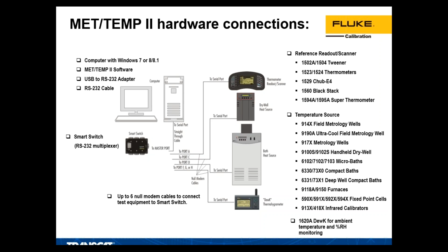In the setup, you choose your reference readout and your temperature sources, and you can even collect data from the 1620A DewK temperature and humidity monitoring unit. That way you don't have to manually record the temperature and humidity during the test — it's all done automatically, which is another great reason to automate this way with software.